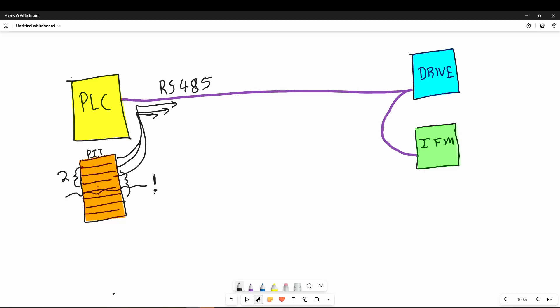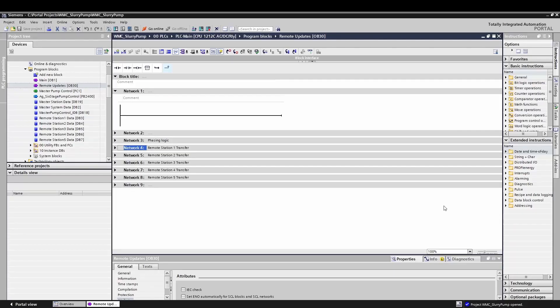So, because of this problem, Siemens has designed two blocks to make sure that your data always stays consistent when using the serial connection, DP read data and DP write data. These blocks grab a full snapshot of the data to be sent and make sure that the data doesn't get updated until it has been sent or received. Don't worry about how this is happening behind the scenes. Just know these blocks have been around for decades, saving engineers like you and me from annoying problems that only happen on your day off. But let's take a look at the structure of these blocks.